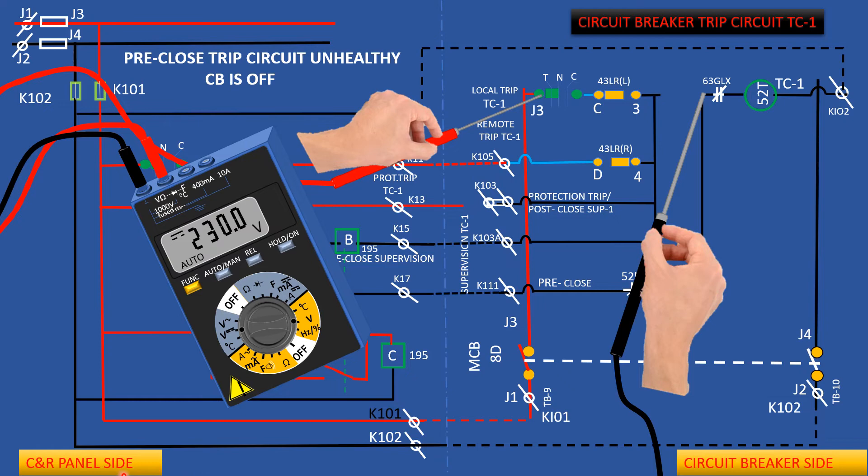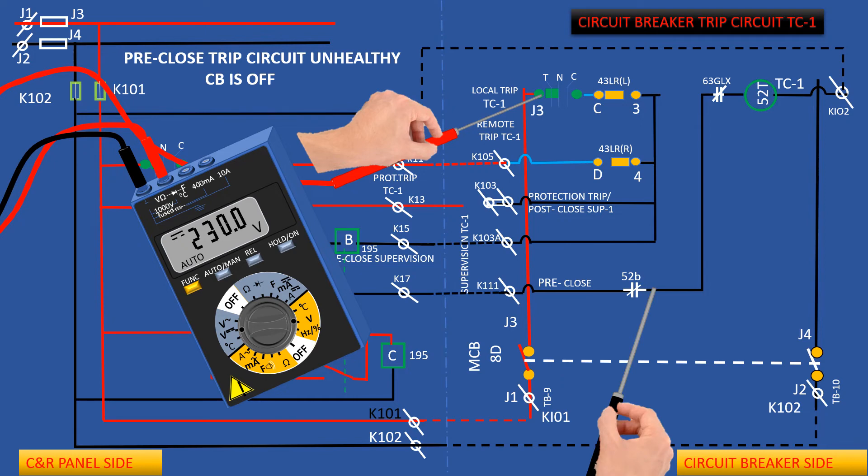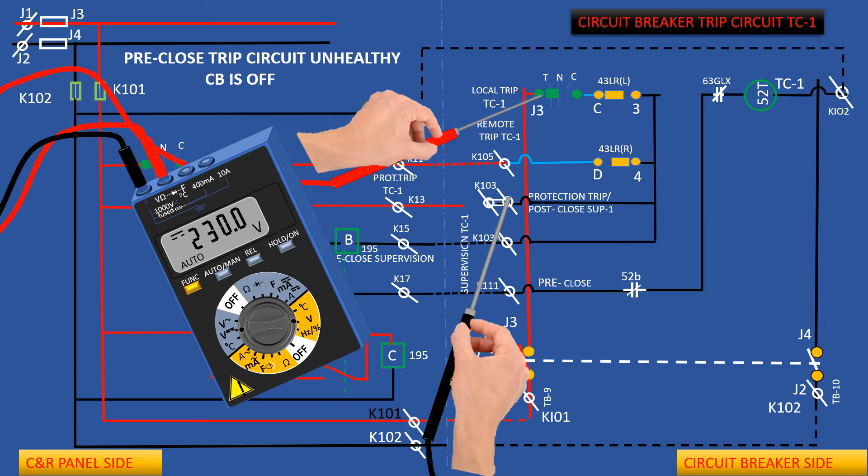Multimeter shows 230 volt DC, that means it is okay. If zero volt would be shown by the multimeter here, then we shall be sure that fault would be at that location. Identify where the problem is situated. Check connection, contactor, etc. of related parts.